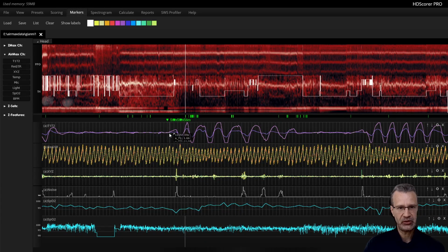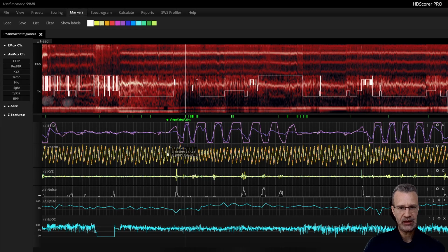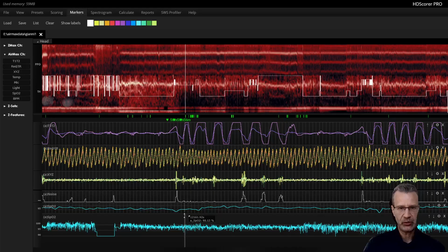The reason I said there's some defects is because here it seems to keep stimulating, so it's not just one time, but it's 3 times, even after you resume breathing. So that's gone now. So just look at this one. It stimulates. Now, how do you verify that? Well, you have the accelerometer, which produces some signal because the whole device is vibrating. And you can see that as soon as this happened, the person resumed breathing.